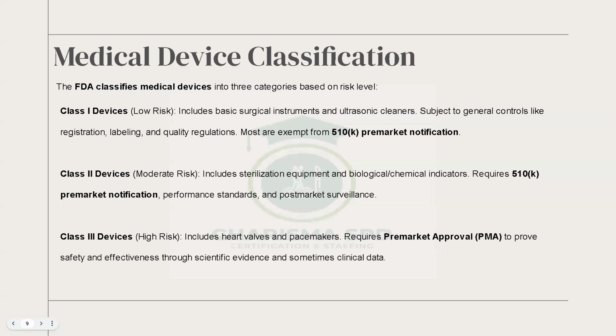So, medical device classification. The FDA, because they have oversight over the medical devices that we handle as professionals, have 3 levels of classification that they have put all the medical devices that come into the healthcare system in. Okay, so with this slide, let me take it myself. So, what is a class 1 device? A class 1 device is classified by FDA standard as low risk. This includes basic surgical instruments, the scissors, the towel, sponge sticks, the Addison forceps, all the simple basic instruments that you'll be seeing very soon, once you are done with this course, are classified by FDA as low risk.